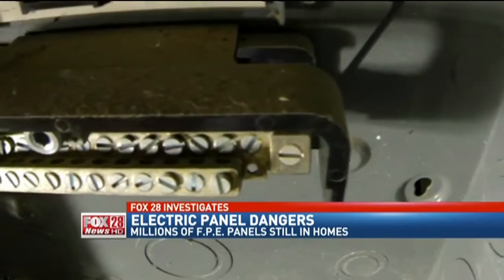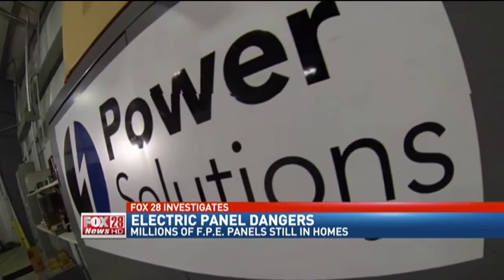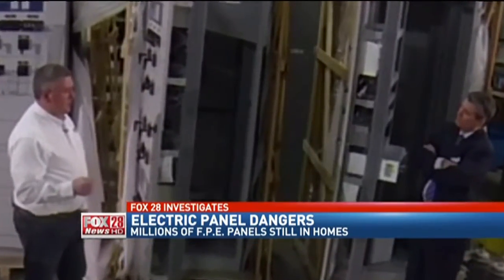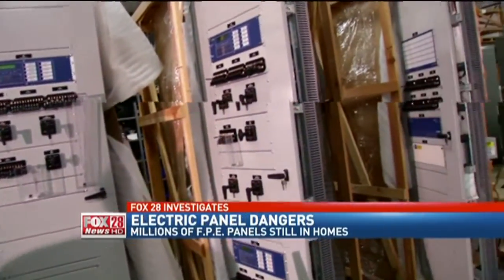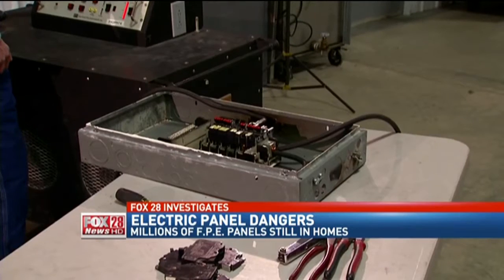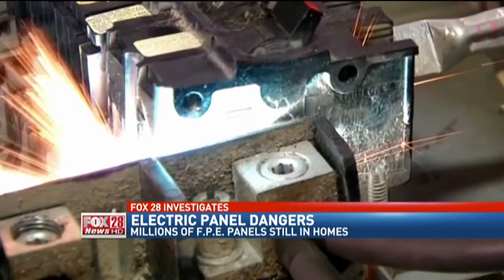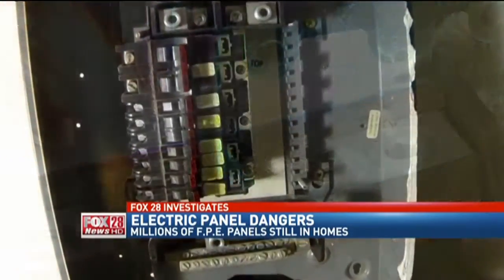Roy says replacing his panel has been on his to-do list and has cost him some sleepless nights — it's a fire risk. I worried too, and wanted to know how dangerous my panel really was. So once Steve removed it, we took it to Power Solutions Group, a company that tests and maintains large power electrical systems, sometimes using enormous circuit breakers on high-voltage transmission lines that can disconnect power to cities. The test simulates an overload on the breaker to see if it can handle it. My panel failed the tests over and over again — it threw quite a few sparks and wasn't able to carry the higher current indicative of a fault, which could have led to a fire. They also found previous burn marks inside my panel wall.